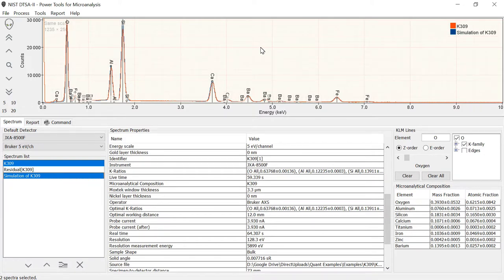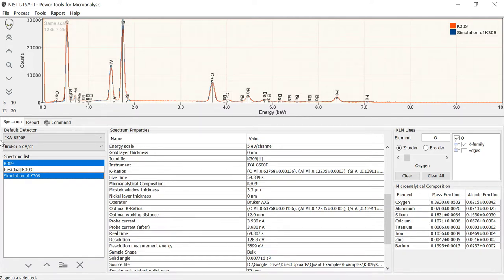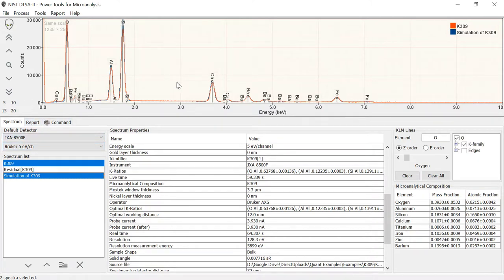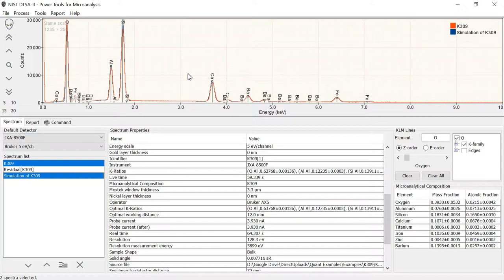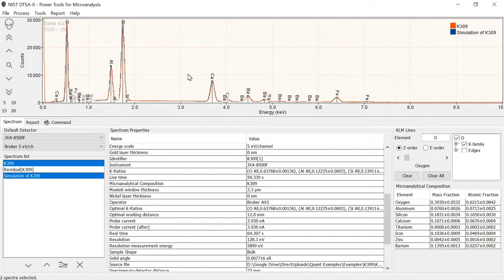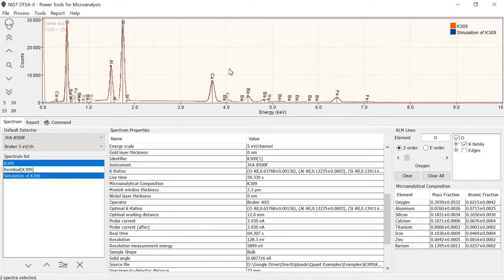We're going to talk some more about that. But largely it's because we've set up our detectors correctly. So this default detector is set up with certain pieces of information that allow us to actually simulate dose-correct spectra. By dose-correct I mean that if we input the correct dose, the product of the probe current times the live time, that the simulated spectra will look both right in shape, but also in relative intensity. And this is a very powerful thing to be able to do.